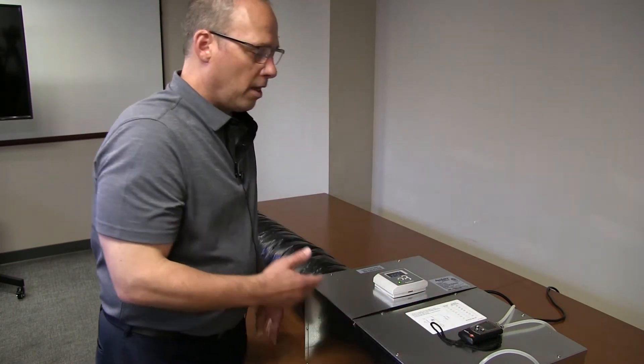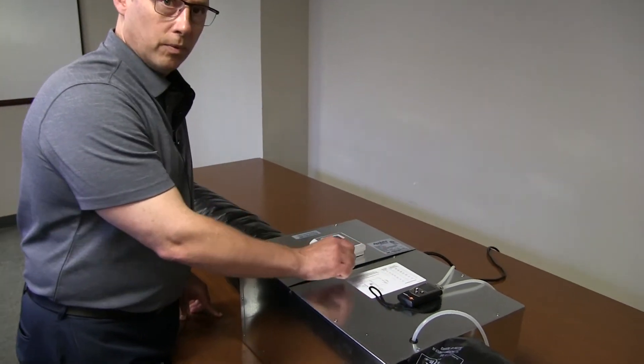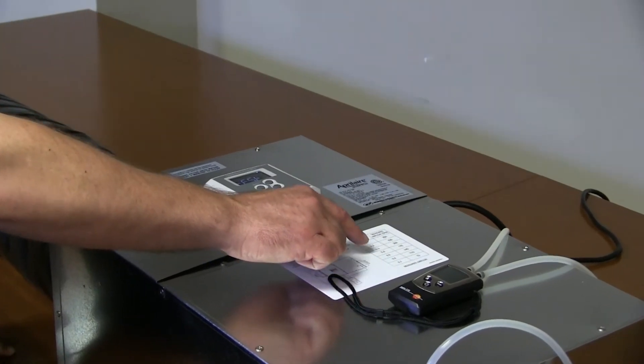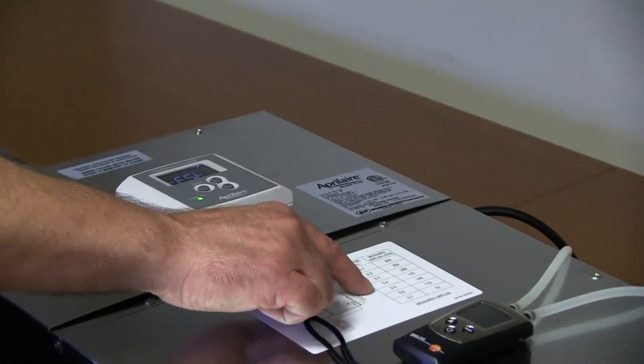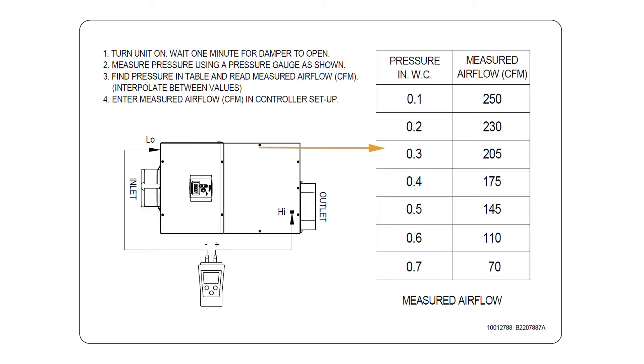So once the damper is open and the pressure reading stabilizes, here we see it's 0.33, that indicates your airflow. So we take that pressure, 0.33, we come to the table that's mounted right on the unit, and we can see that we have a 0.3 and a 0.4 reading. The 0.3 reading is 205 CFM, the 0.4 is 175 CFM. Our reading is 0.33, so it's pretty close to the 205 side. I would estimate our airflow here to be 195 CFM.